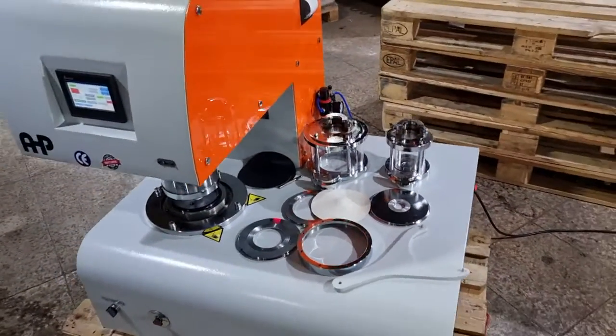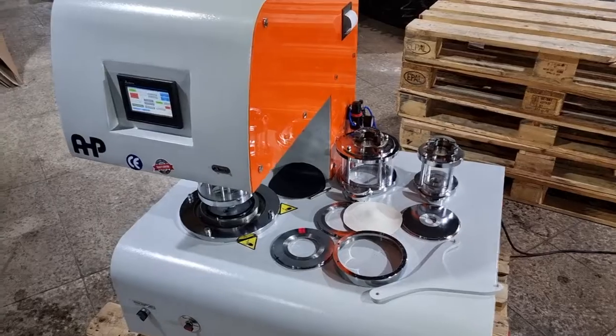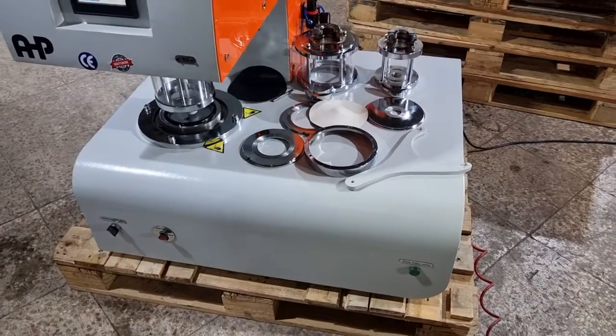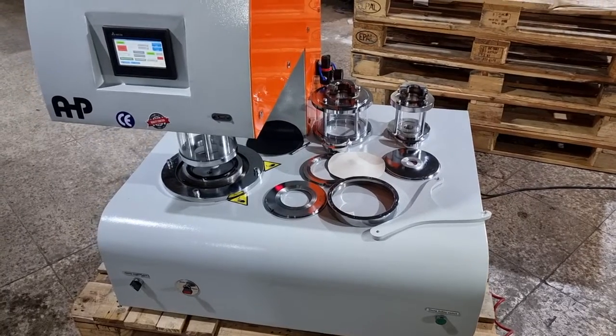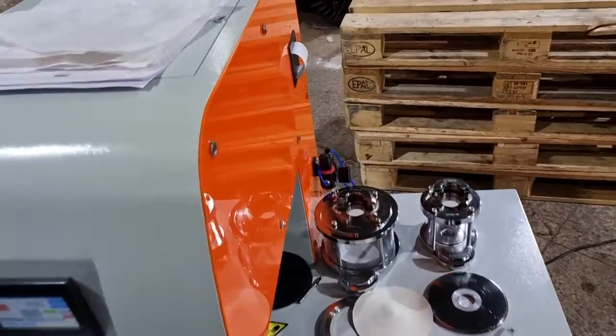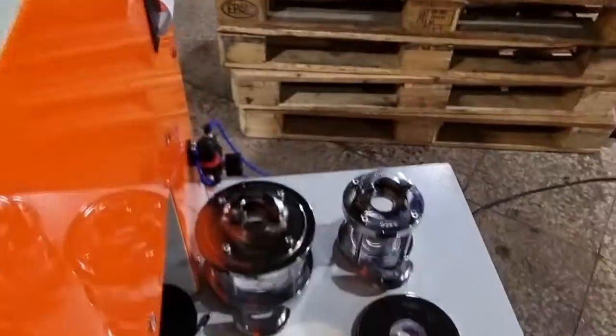In this video I'm going to demonstrate how the hydraulic burst testing machine from AHP Plastic Makina is working. This is the hydraulic model — the maximum pressure depends on the customer request, and it comes with the requested test area and test sample clamp sets. The machine is according to ISO 13938-1.